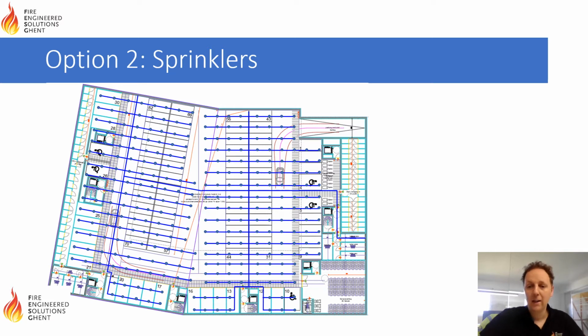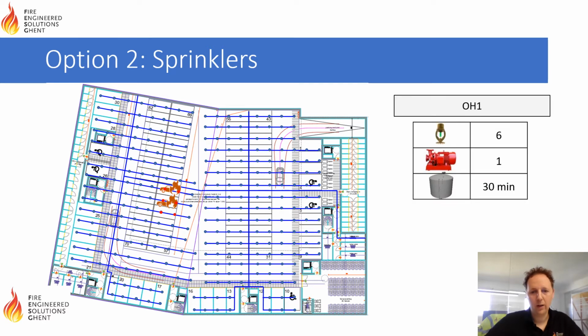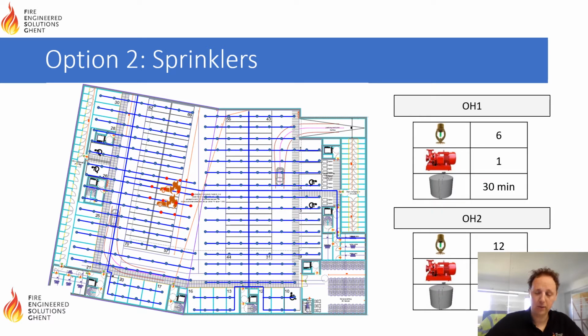Second option would be to put a sprinkler system in a car park where, according to the European standard, you would look at a risk classification of ordinary hazard 2, where the sprinkler would be dimensioned on 4 sprinkler heads plus a redundancy of 8 sprinkler heads around it, and based on that you would dimension the sprinkler. Some jurisdictions would allow for a smaller risk classification OH1 if the car park is of limited size.